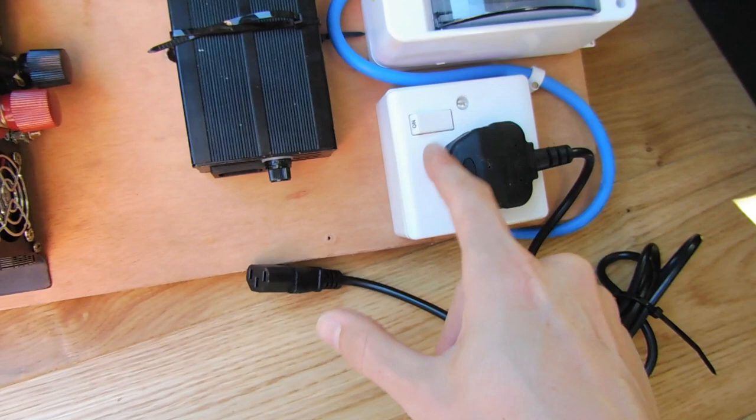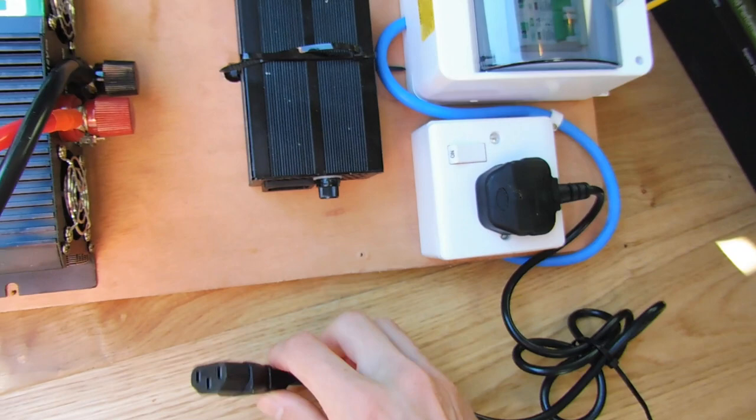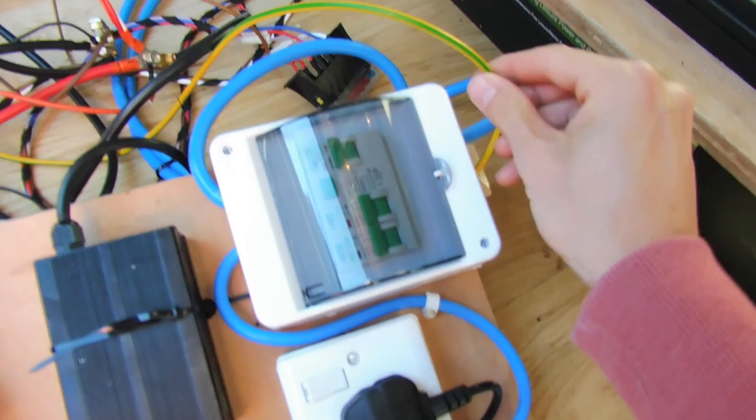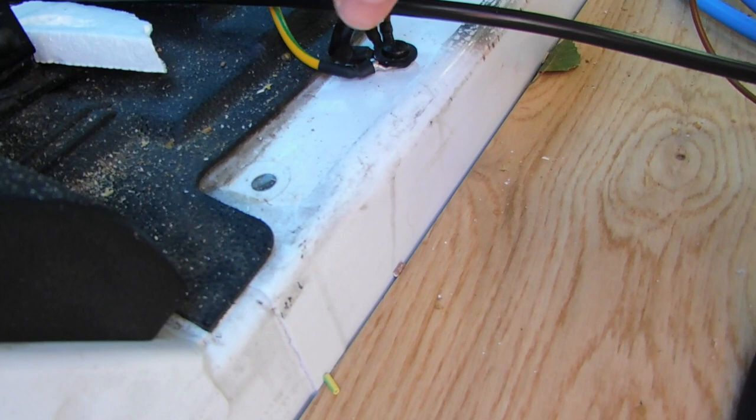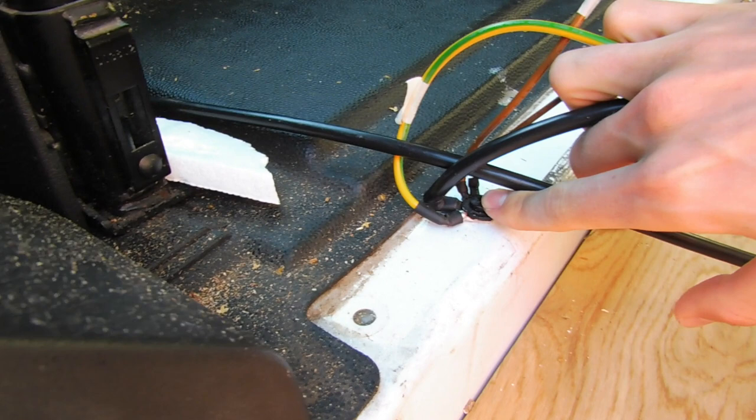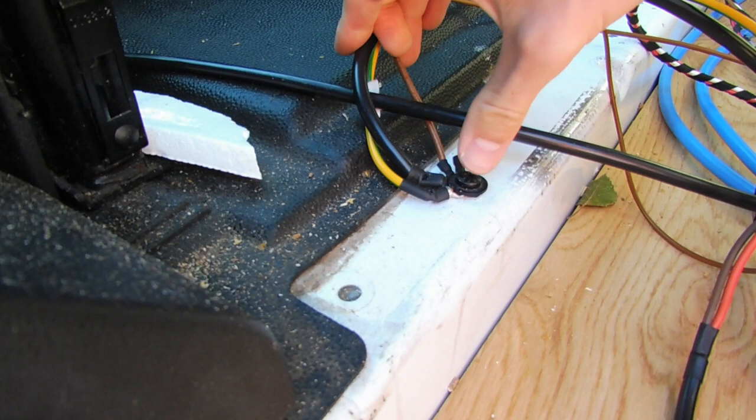Last but not least, you have the earth cable, and that runs all the way to my grounding point that I put here. It's one of the bolts I had on the back here that held down part of the bulkhead. What I've done is I've taken one of the bolts that was already there, and before I put all these down, I sanded off the paint so it's raw metal and screwed all these guys down, so they should be earthing quite well to that point.